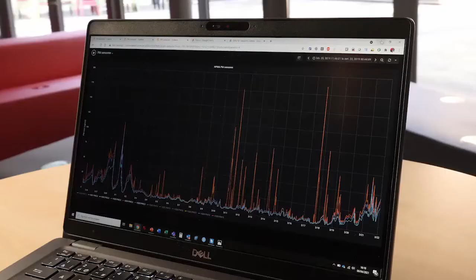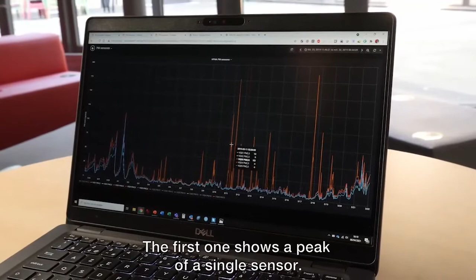When you're working with low-cost sensors, you often find data that's strange or just impossible. Here are some examples of data that didn't survive the validation process. The first one shows a peak of a single sensor. That's not impossible, but when it only happens to one of the 5 units, it's probably something going wrong with a single sensor. Here's another case where one sensor gave a spike that was always on the hour or half hour. That's probably some sort of electronic interference, but we didn't find out what it was.